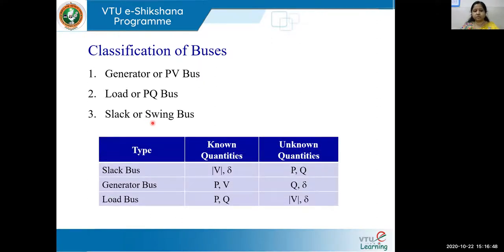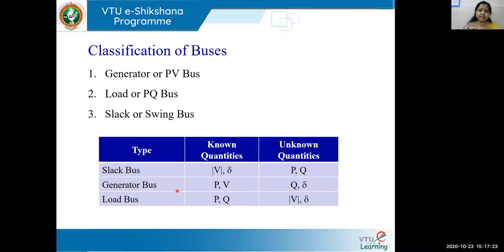In the table we have three types of buses. For each bus, out of the four parameters — real power, reactive power, magnitude of voltage, and angle — two are known and two are unknown. For the slack bus: known are magnitude of voltage and angle; unknown are P and Q. For the generator bus (PV or voltage control bus): known are P and magnitude of V; unknown are Q and delta. For the load bus (PQ bus): known are P and Q; unknown are V and delta.